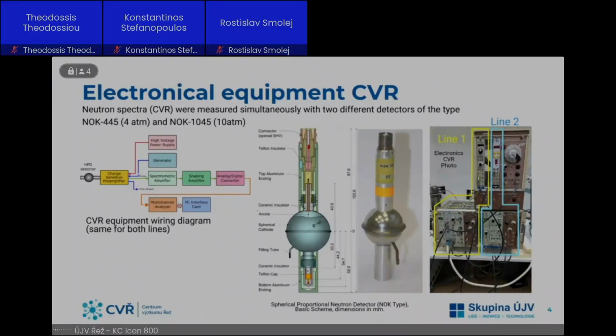For the people who are involved as electronic engineers, there is a scheme or wiring diagram of this. It contains the hydrogen proportional detector, which is a small sphere with a diameter of about 40 millimeters, filled with hydrogen. The spectra measurement is based on the method called the proton recoil method, where the neutrons enter the nucleus of the hydrogen, giving energy to the protons, and the protons are ionizing, and the electrons are collected on the anode of the detectors.